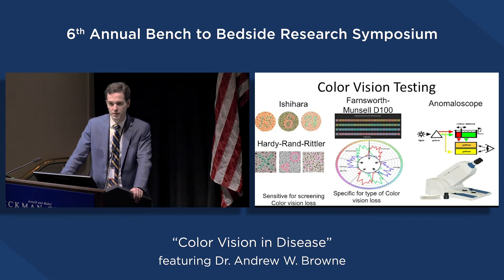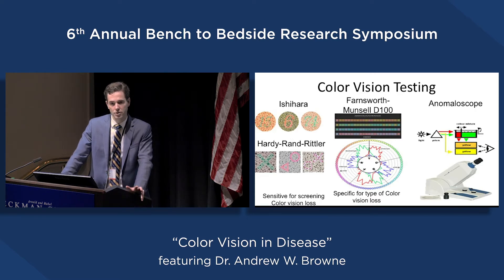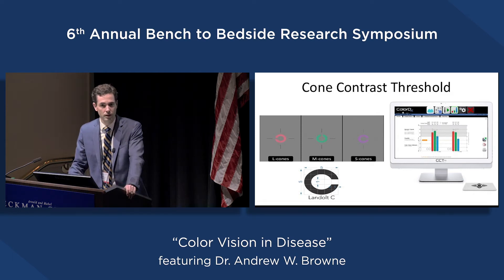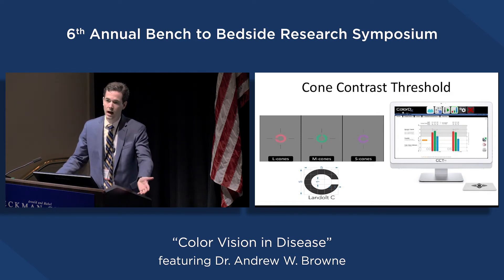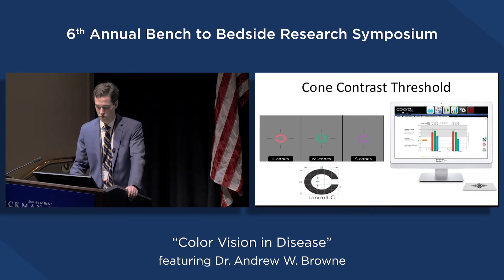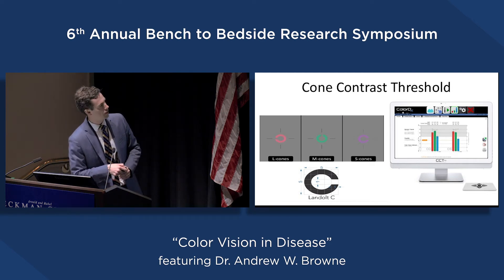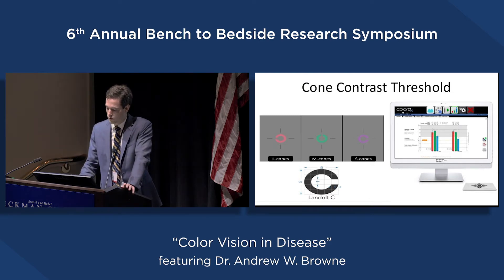The anomaloscope is a test where you compare the combination of green and red to a reference yellow to determine how much error there is — but again, this is another 20 to 30 minute test not practical in the clinical context. Dr. Jameson has already shown us how the cone contrast threshold works. It's very useful because it's a highly calibrated computer screen that can control exactly how bright different letter C's are presented to a patient, and provides individual sensitivities of the red, green, and blue cone classes in each eye.